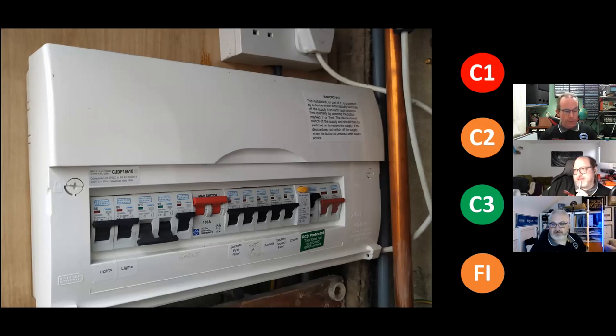I would sit down square in front of that enclosure and look at the impact the pipe makes for me to safely work on that panel. And if working on that panel is compromised by the presence of that pipe, I would consider an impact with regards to maintainability and accessibility, and I'd probably use Electricity at Work Regulation 15 to say that it's not as safe as it could be to work on. Yep. Okay, so what does the survey say?